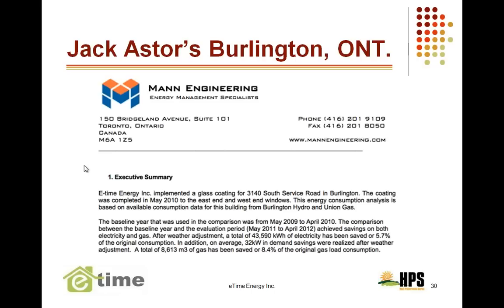We achieved savings in both electricity and gas. The weather-adjusted figures show savings of 43,590 kilowatt hours of electricity, a 5.7% savings on the bills, and a 32 kilowatt demand savings on peak load. Gas savings were 8,613, rendering an 8.4% reduction in gas consumption. On average, we saved about 7%.